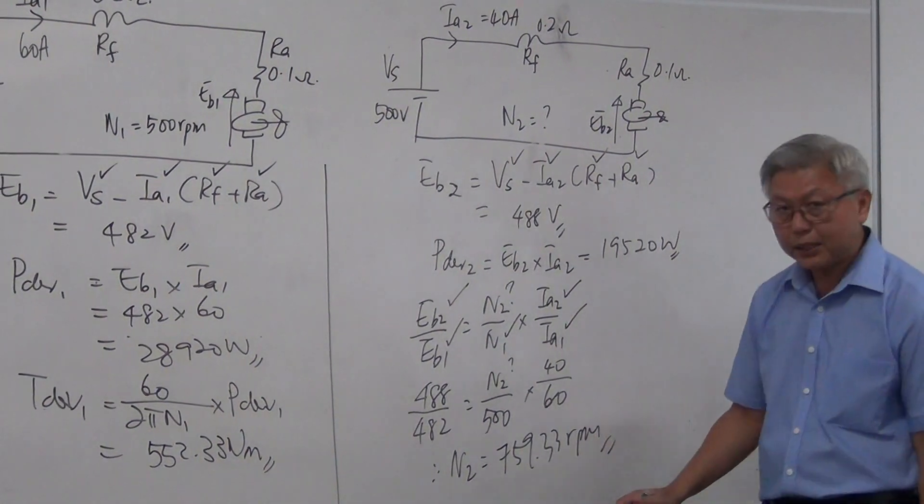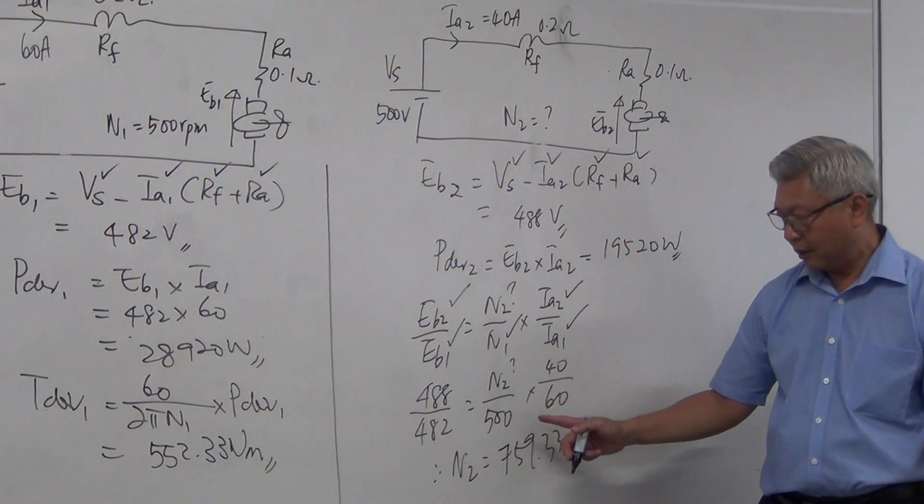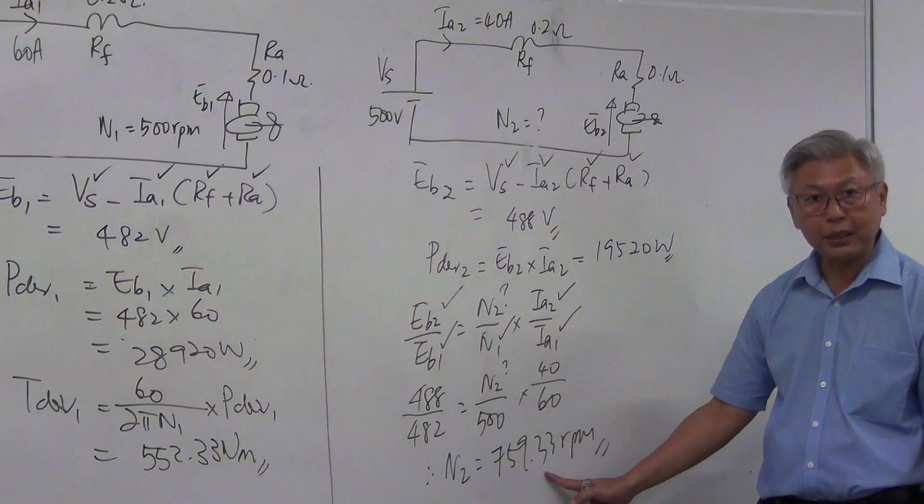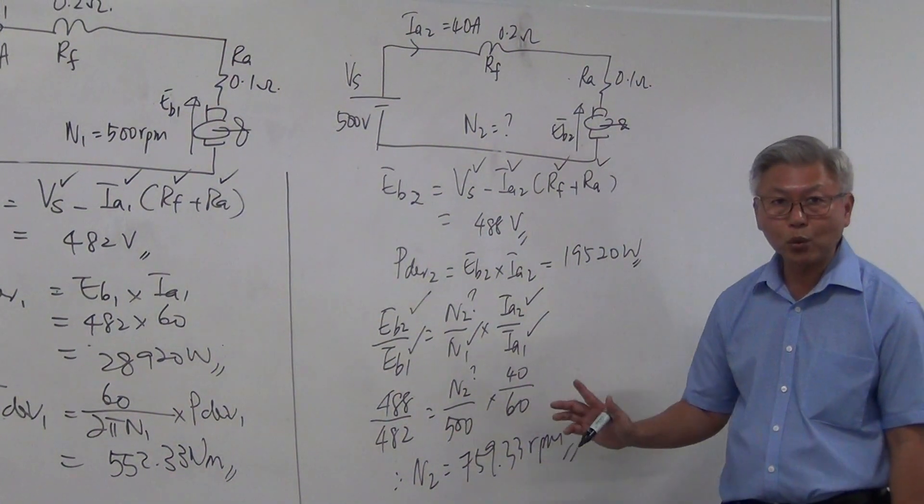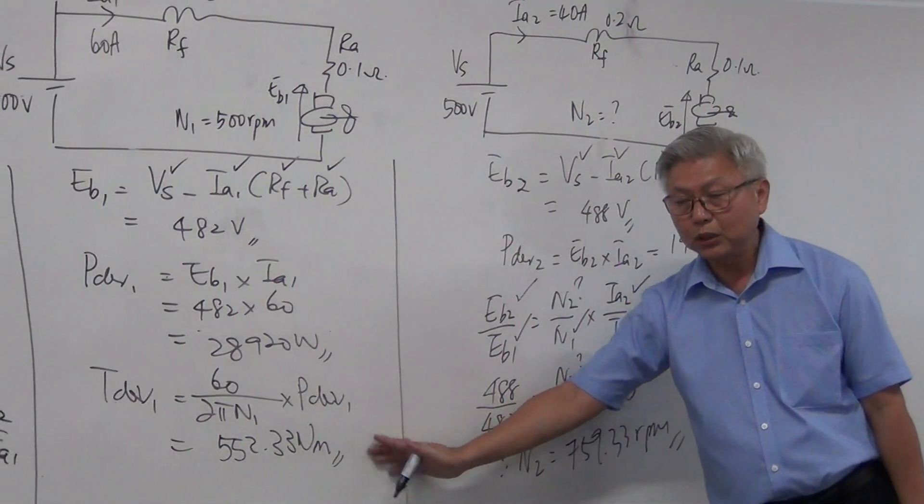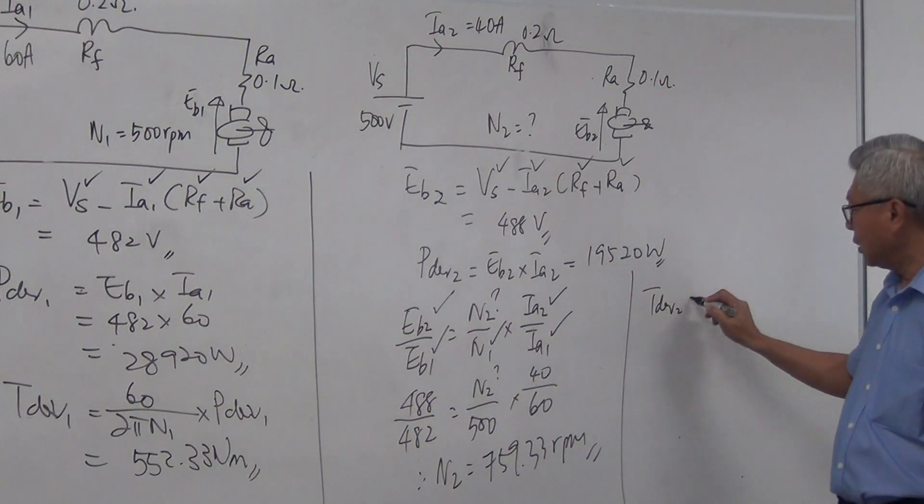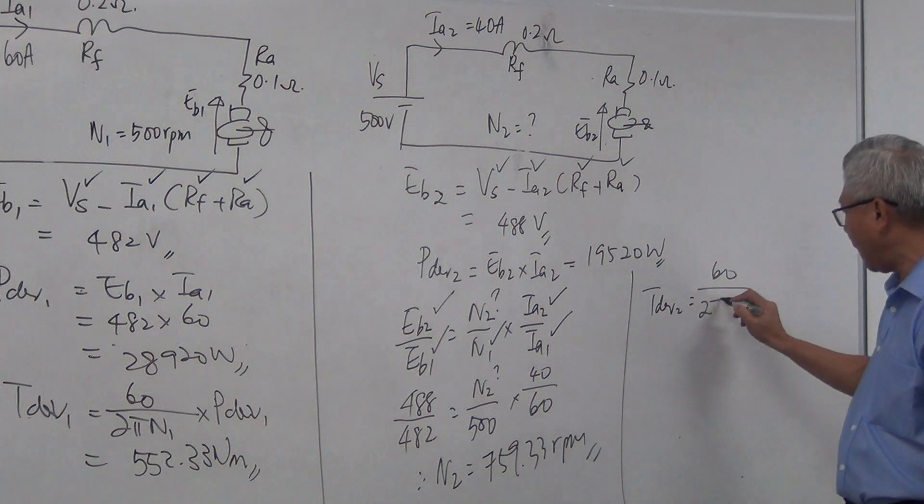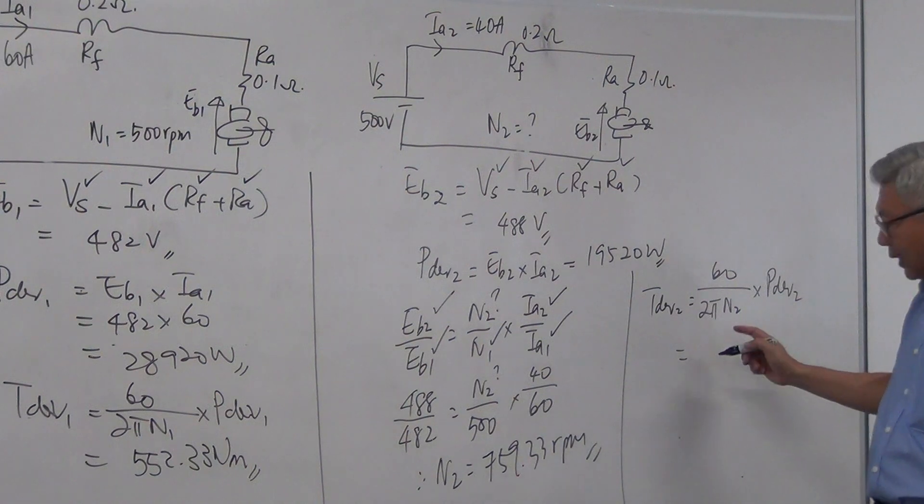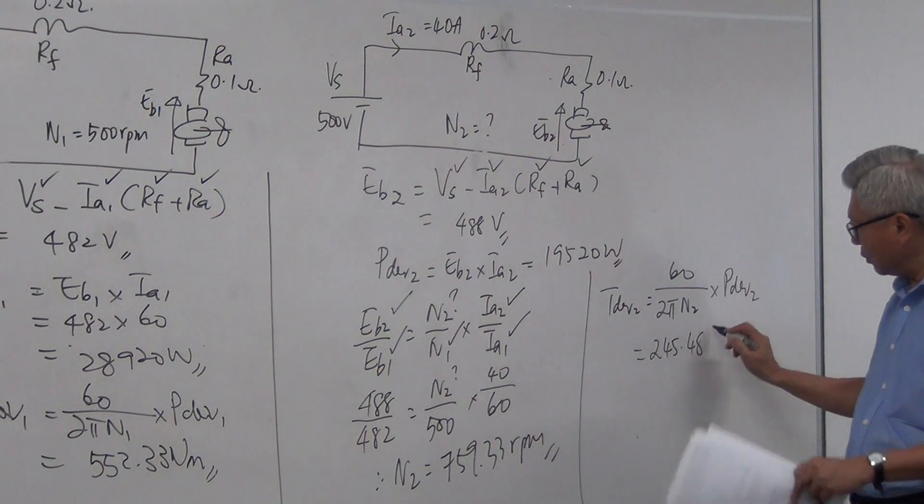Can you see? There is now a lot of changes in the speed with the change in torque. It was 500 RPM, but now it's 759.33 RPM. So this is the difference between shunt motor and series motor. And the original torque was 552 Nm. How about this new torque now? If I were to calculate the new torque using 60 divided by 2 pi N2 multiplied by power developed 2 formula and substitute the values, I would get 245.48 Nm. So that is the difference in the torque, and also a big difference in the speed.